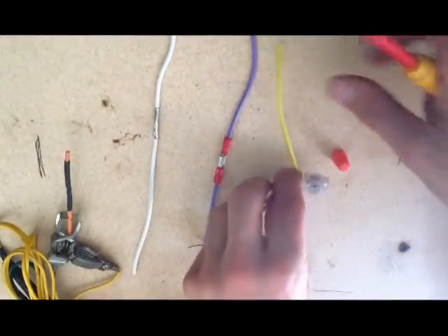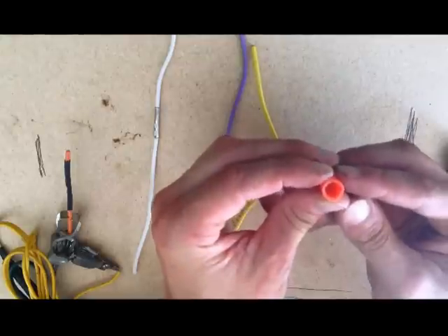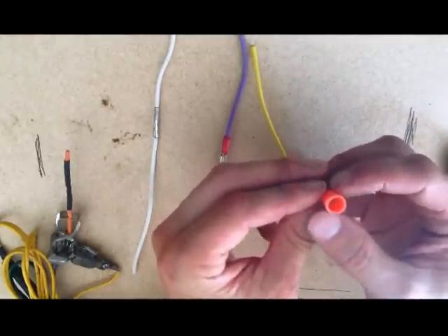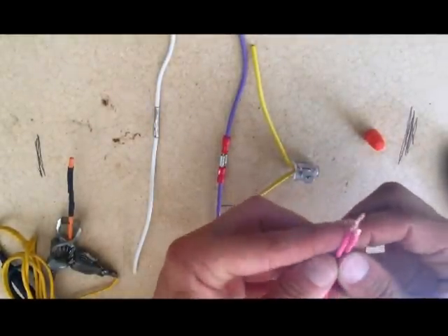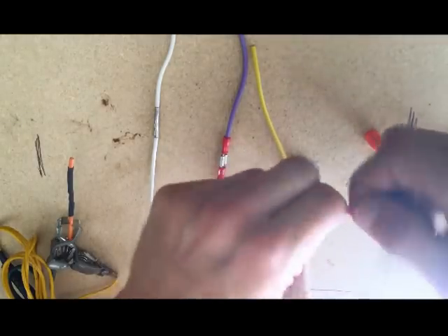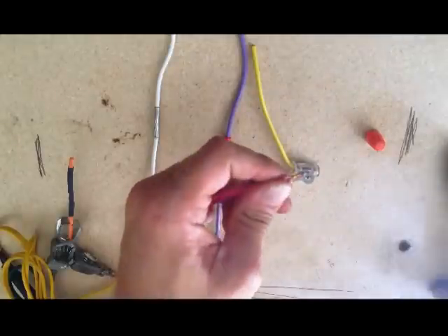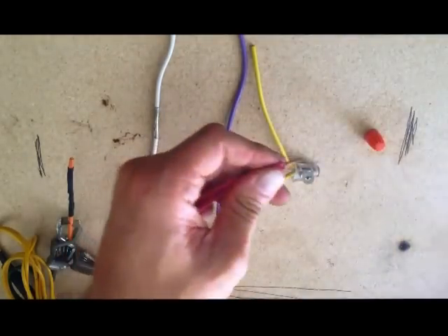Okay. So that's another good little joiner. And then the last one I'm going to do is a wire nut. So these have got a fairly sharp thread on the inside and they bite down on the copper when it's twisted on top of them. Okay. For that, the same again. A fairly long piece of exposed copper for us to twist together by hand. And then just the same with the bullnose pliers. Twist them together. Just gently. And that gives us a good connection. And then with your wire nut, just wind it on. Nice and snug.